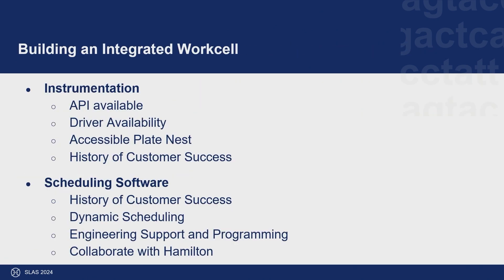What does it take to build an integrated work cell? We had to find the proper instrumentation. Proper instrumentation for integration means an API is available and a driver is available either for our automated liquid handler or for our scheduling software. Any instrumentation also had to be automation-compatible — meaning it has either automated doors or an accessible plate nest for a robotic arm. Very important to me was having no guesswork: I wanted instrumentation that I have either used myself with success or that a trusted automation colleague has used with success. The same goes for scheduling software. I needed a scheduler with a history of customer success — I have been using Green Button Go for 12 years, probably back to its first iteration, and I knew that was the scheduler I wanted to use. I didn't want a learning curve.